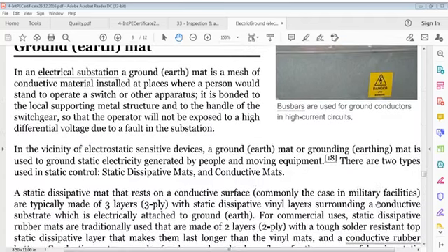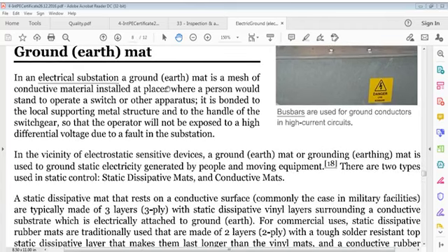In an electrical substation, a ground mat is a mesh of conductive materials installed at places where a person would stand to operate a switch or other apparatus. It's bonded to local supporting metal structures and to the handle of the switchgear so that the operator shall not be exposed to a high differential voltage due to a fault in the substation.